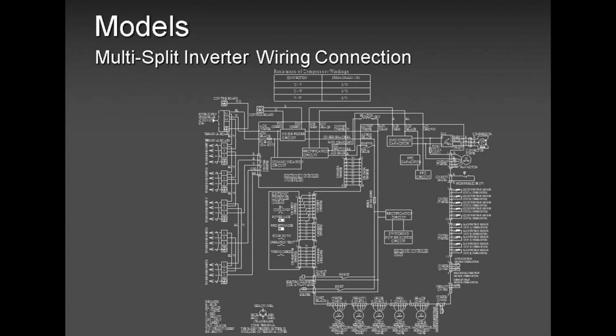This slide shows you electronic expansion valves. So we are talking again about 5 zones. If we were talking about 2 zones, you would see only two of these electronic expansion valves, A and B, that's it. And if we were talking about 3 zones, A, B, and C. 4 zones, A, B, C, and D. But we are talking about 5 zones now, so it's A, B, C, D, and E. So when you power the unit for the first time, this electronic expansion valve will start clicking. If you don't hear those clicks, my friend, you have a problem already. So always remember, when you power the unit for the first time, whether it's a multi-zone or a single zone, you need to hear the clicking of that electronic expansion valve or linear expansion valve. They're all the same thing. It depends on which manufacturer you're working on.